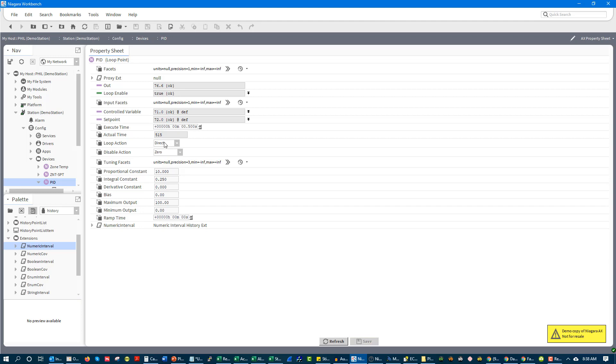Direct acting is when you go above set point. When the process variable goes above set point, you're going to increase the output. And reverse acting is when the process variable goes below set point, you're going to increase the output. So you could naturally think that for cooling, things like cooling, things like CO2 control, those would be direct acting.